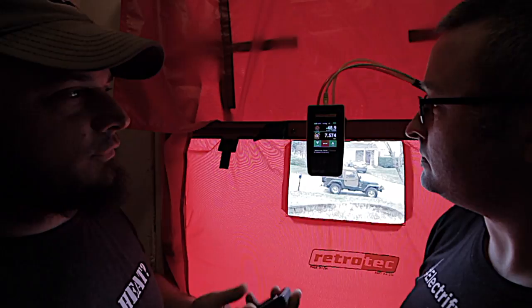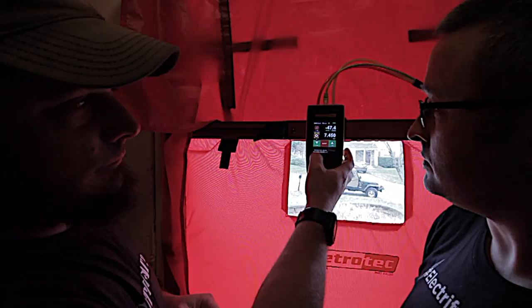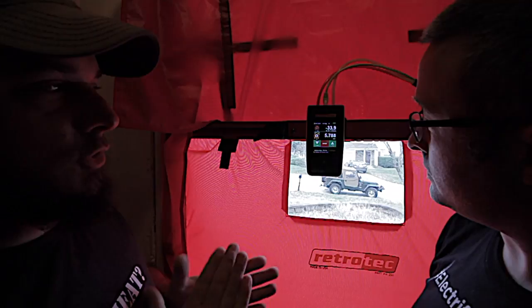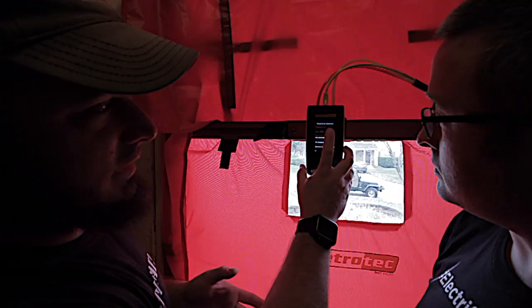And we're going to set our pressure down to 25. I don't remember where we started and how many times I pushed the button. Two more. 35. One more. 25. There we go. Okay, so we're going to seek 25. And we're down to about 12% blower speed right now. And we're going to go back to CFM flow.